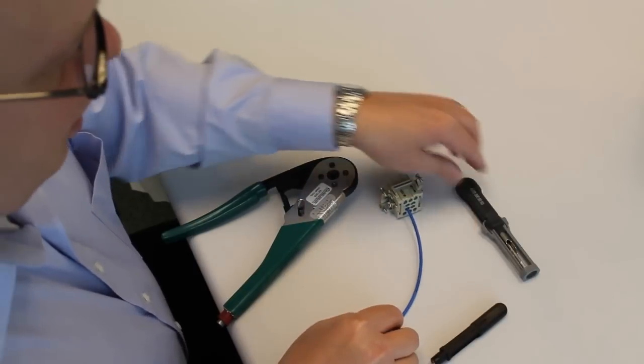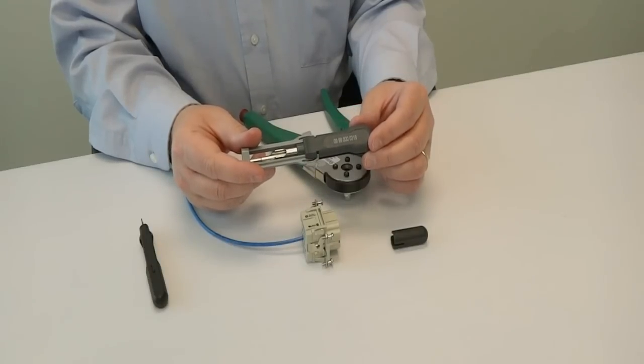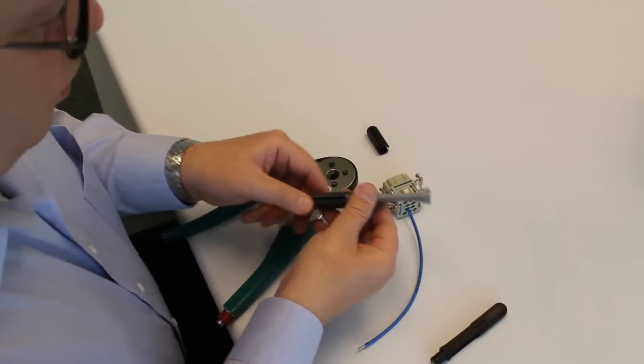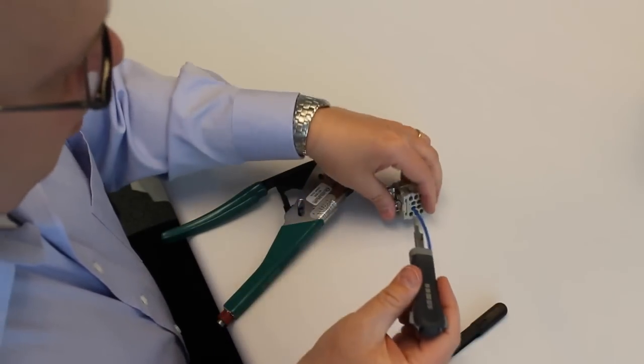The contacts can be easily removed by using the removal tool, part number 0999-000-0319. There's a safety cover to prevent damage to the tip and the operator.